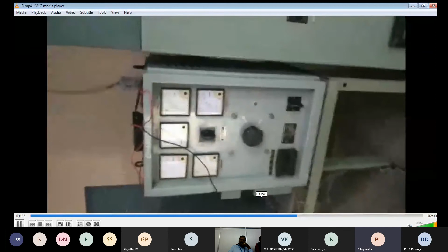This is a DC distribution panel. This DC distribution is required for controlling the breakers, for the tripping coil and closing coil. This is a battery charger. In the substation there is a DC battery available, this is a charger, and we have a standby charger also, main charger and standby charger.